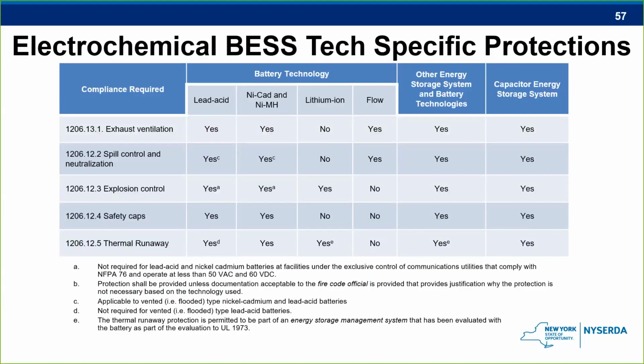I'll reiterate again that in New York, we anticipate the market will utilize mostly lithium-ion batteries, at least in the foreseeable future. So if you look at the lithium-ion column, you'll notice it doesn't require exhaust ventilation, for example, because they don't emit hazardous fumes when they're charging or discharging over the normal course of operations, but they do have the potential to emit flammable gases in the event of a fire. So you'll notice that they do have a yes for explosion control. So that's just one example of how requirements differ for the different technology types. And we'll discuss some of these in a little bit more detail on the following slides.